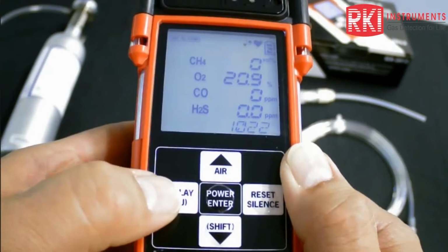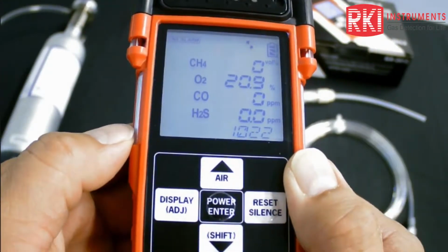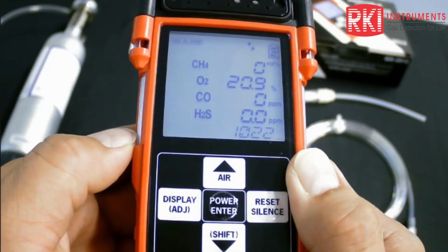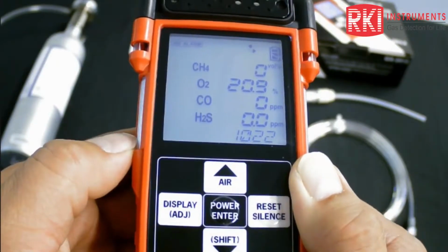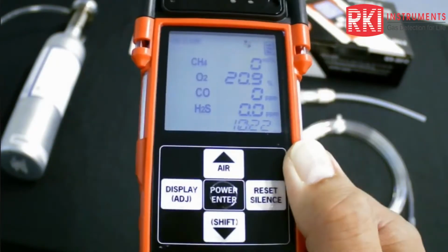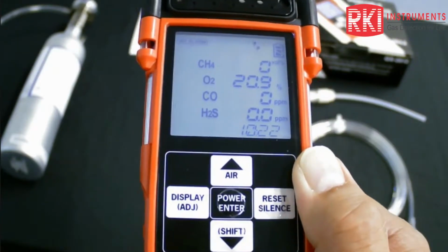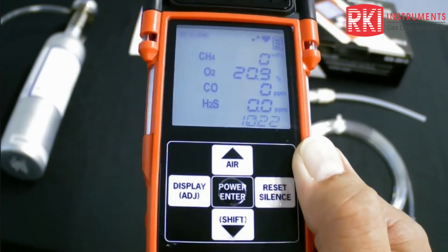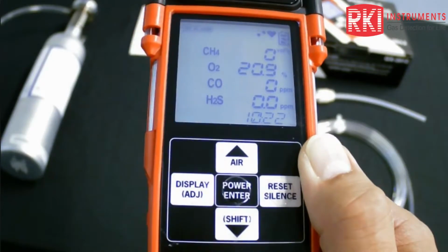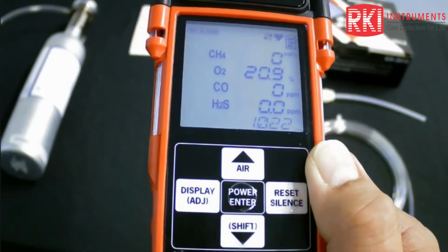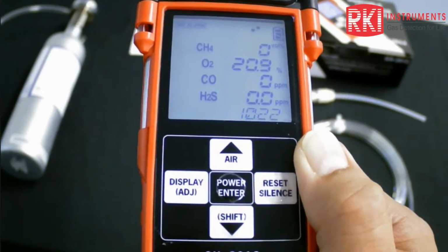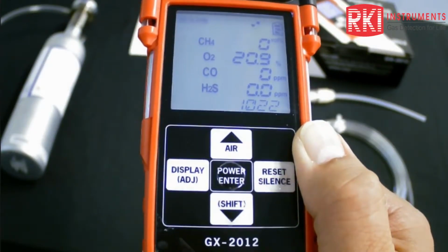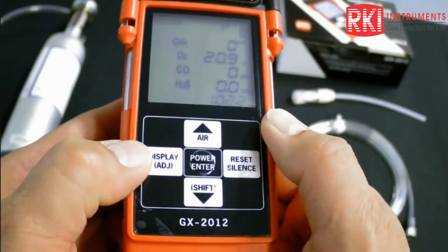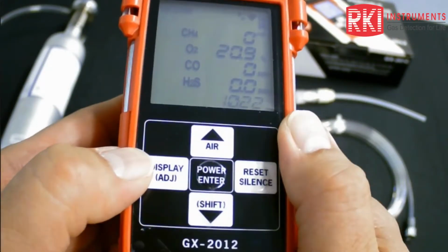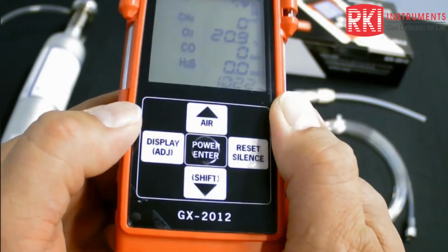So basically, for our purpose, why would you want to just immediately from the get-go take out the auto range and put the volume percentage? Okay, only if you think you're going to hit this thing with a big slug of gas. If you're pretty sure that's going to happen, then you could take out the LEL range and just see how much gas is there, by going into the volume range only. But if you're not sure and you're really concerned with safety first, you can just leave it in the auto ranging, the normal default.